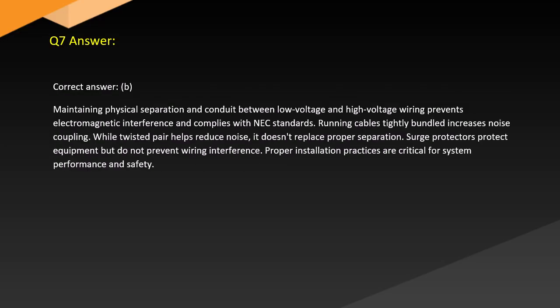Answer. Correct answer: B. Maintaining physical separation and conduit between low voltage and high voltage wiring prevents electromagnetic interference and complies with NEC standards. Running cables tightly bundled increases noise coupling, while twisted pair helps reduce noise. It doesn't replace proper separation. Surge protectors protect equipment but do not prevent wiring interference. Proper installation practices are critical for system performance and safety.